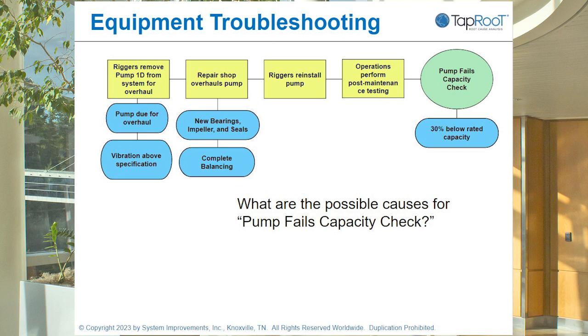Here's an example of a basic pump failure. We had a pump removed from a system for an overhaul. Both our predictive and preventive maintenance told us this needed to happen—it was due for an overhaul per the preventive maintenance schedule, and the vibration monitoring system told us it was above specification. So we uninstalled the pump, took it to the shop for an overhaul, got new bearings, impeller, and seals, and did a complete balance on the pump.